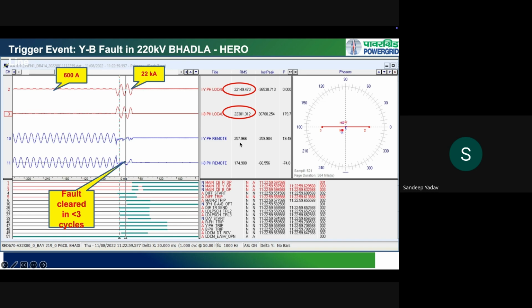As we know, because these devices are current limited, the fault contribution is very, very small. It does not go beyond 1 per unit, which is the rating of the machine. So if you compare with the grid side, the fault contribution from the solar plant is almost negligible. For currents of this magnitude, 257 and 174, it is very difficult for the distance relay to operate, because there is not enough current to start the overcurrent element or the distance element of the distance protection.